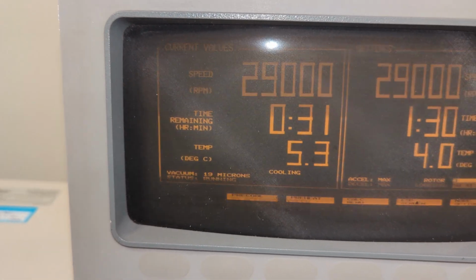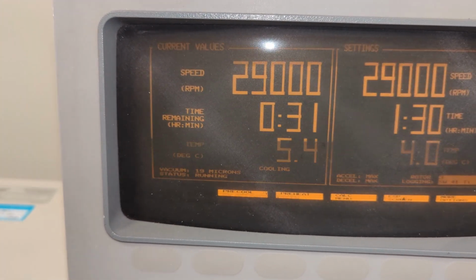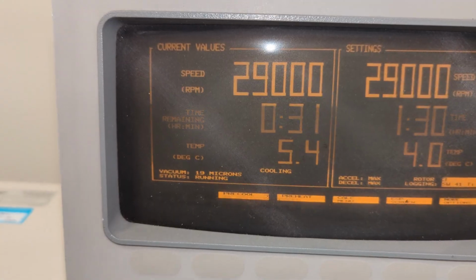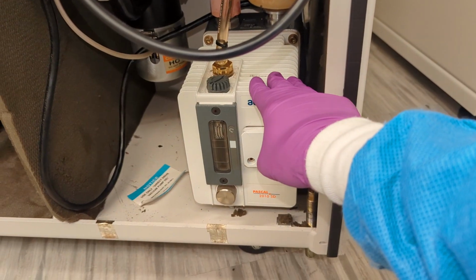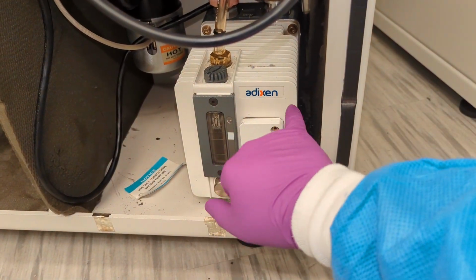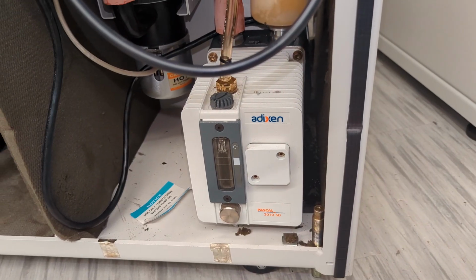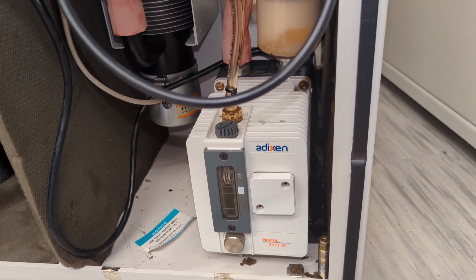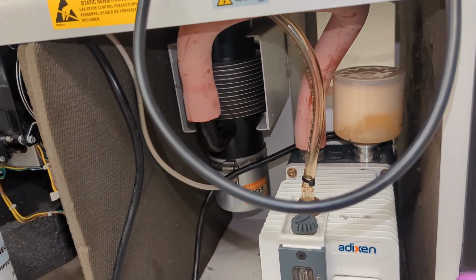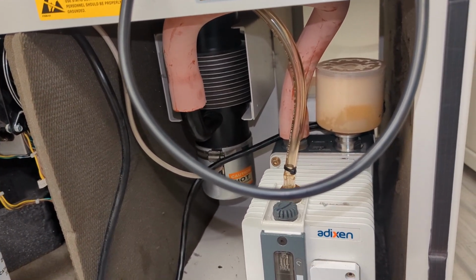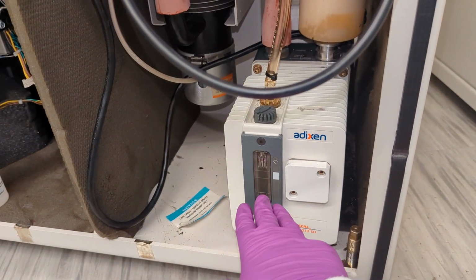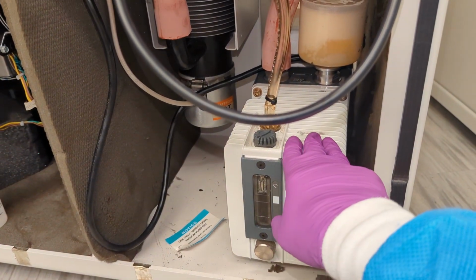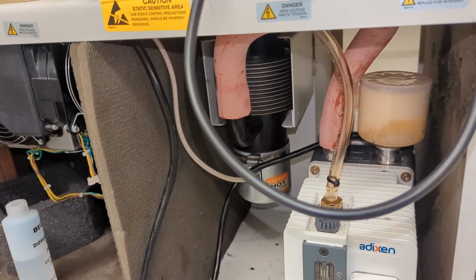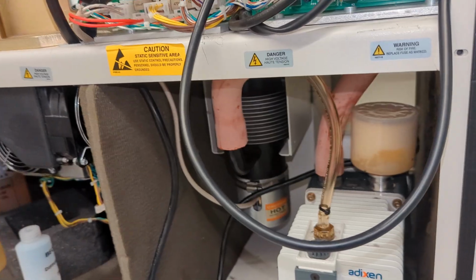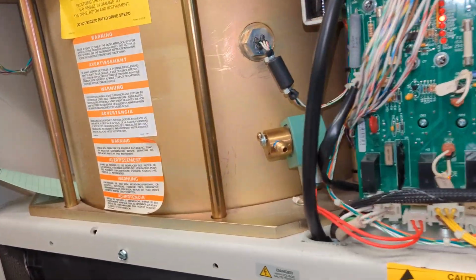But as you can see, this vacuum is hovering around the low end of that spec. And so I've done a couple things already to try to remedy that. One, I basically refurbished the pump, got a service kit from Adixen, and rebuilt the thing, assuming that had never been done before. I replaced the vacuum hose, which was in really bad shape, had a lot of cracks in it, and then also changed the oil for the rotary pump and the diffusion pump, and it has not made any difference.